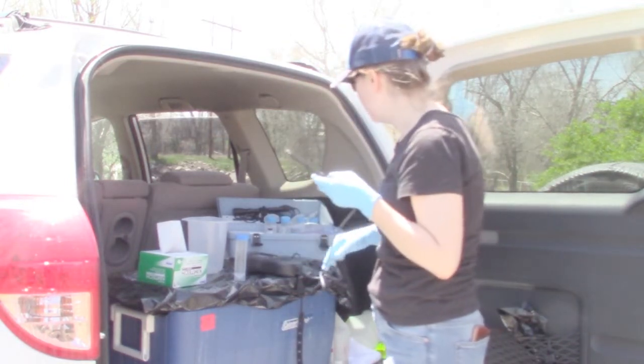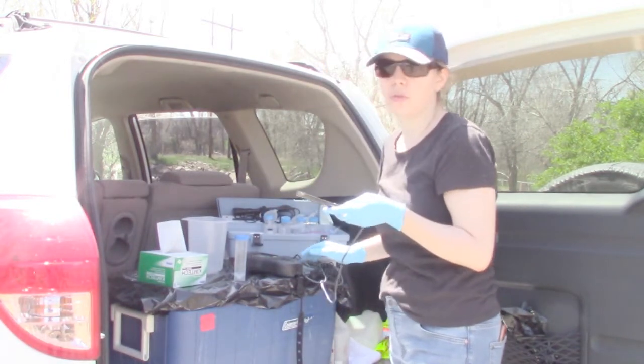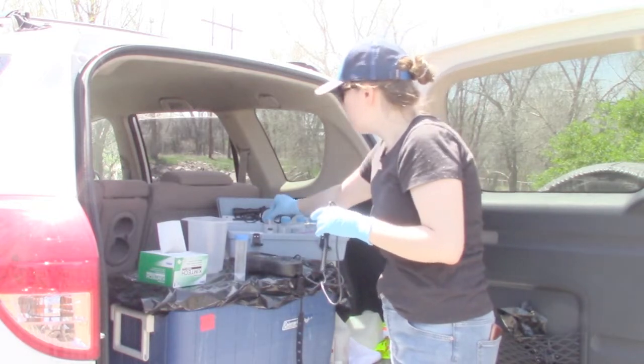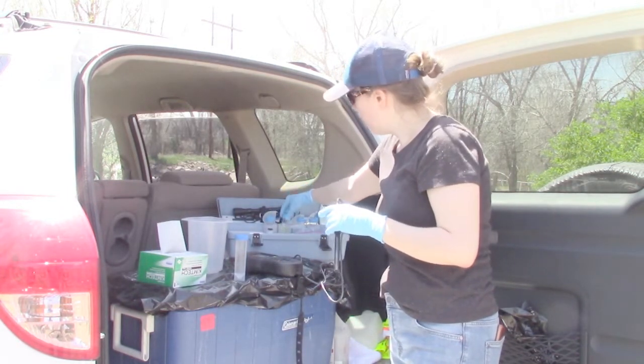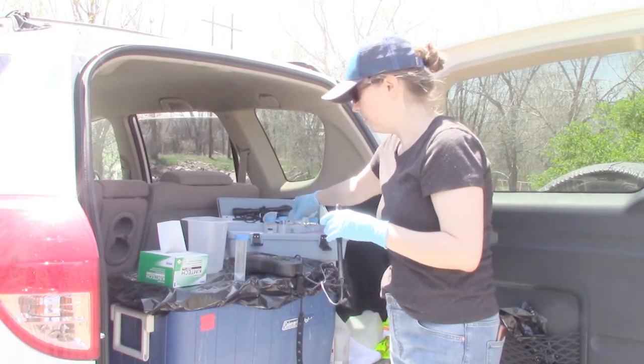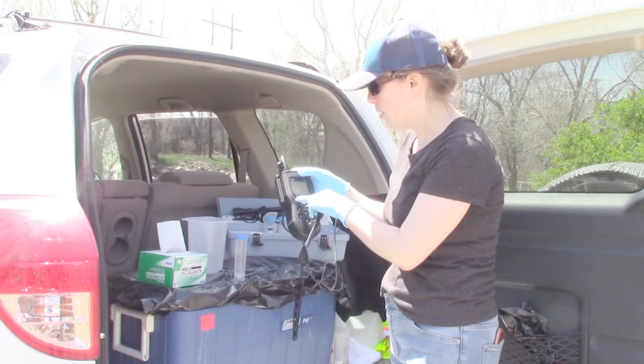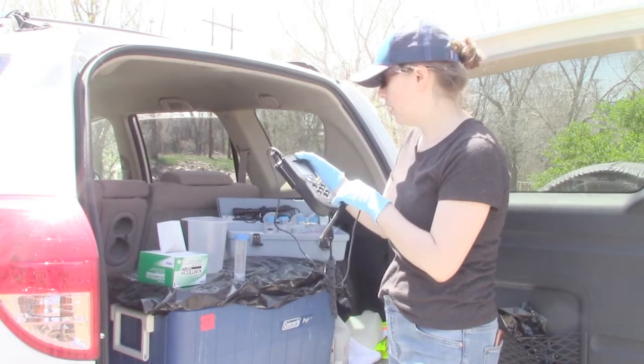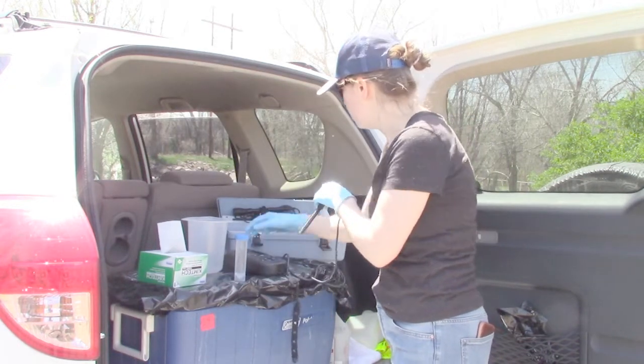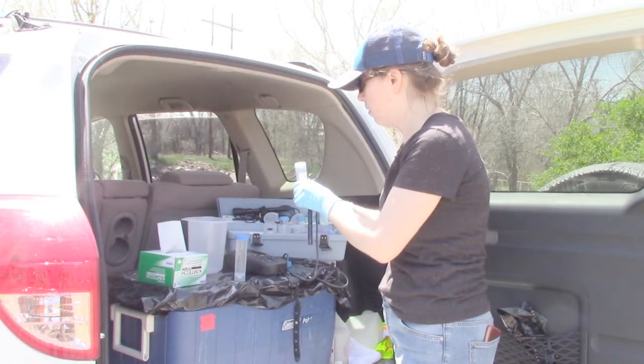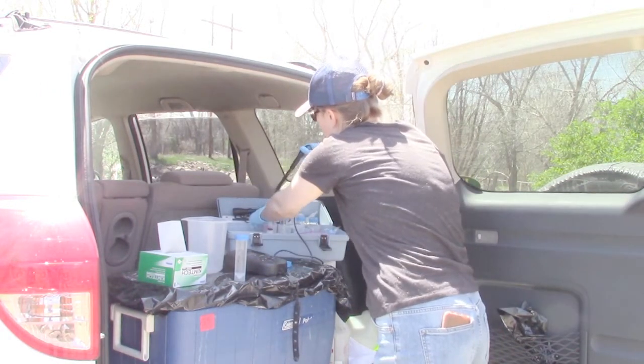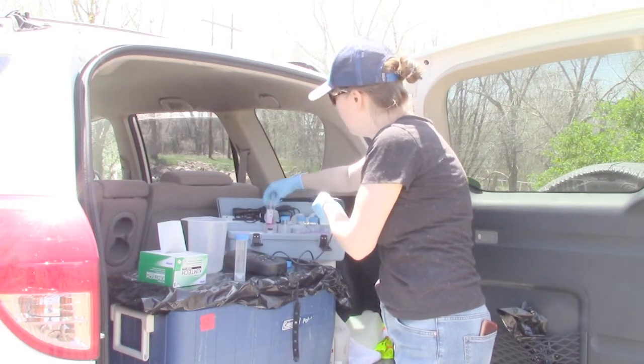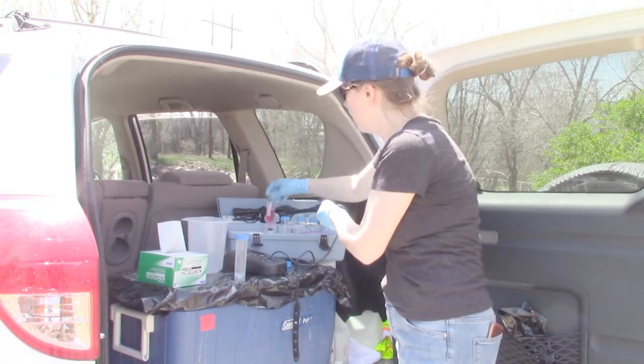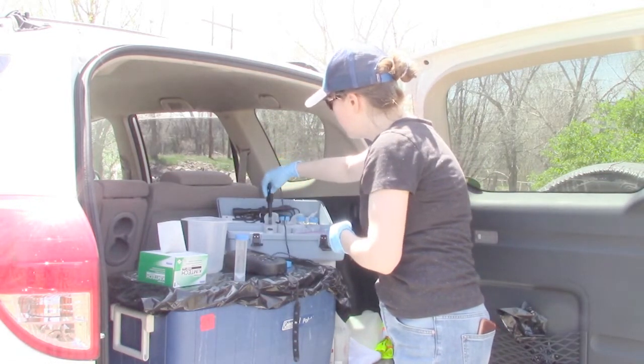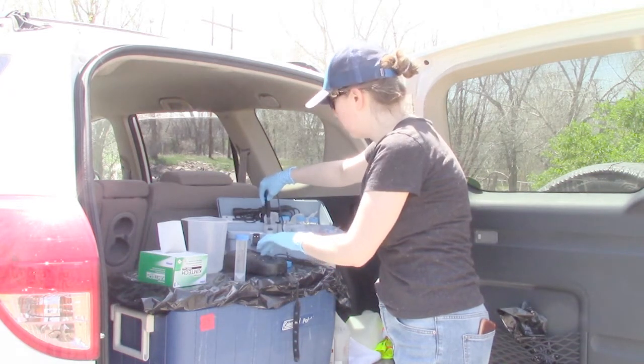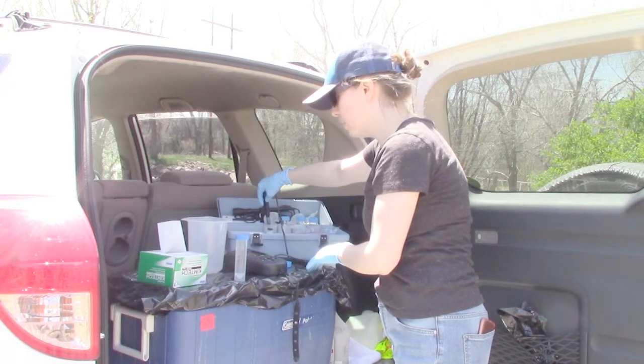I'm going to turn on the multimeter. The first thing we have to do is calibrate the probe. What we typically do is a 3-point calibration, starting with pH 4, then pH 7, and at the end pH 10. So you go to your multimeter here and press calibrate, and it's going to tell you to rinse the probe, which we just did, put it in a buffer and push the read key. That's what I'm going to do. I like to put the tube with the calibration solution in something steady so it doesn't fall. I always give it a slight swirl while it's in there, and then I press read and wait until it's stabilized.